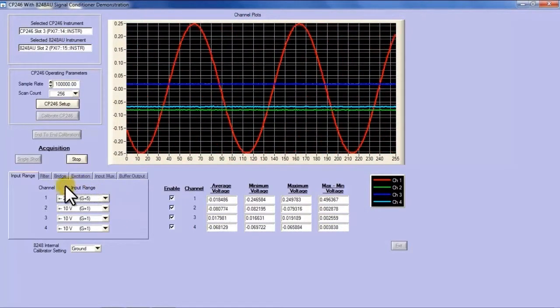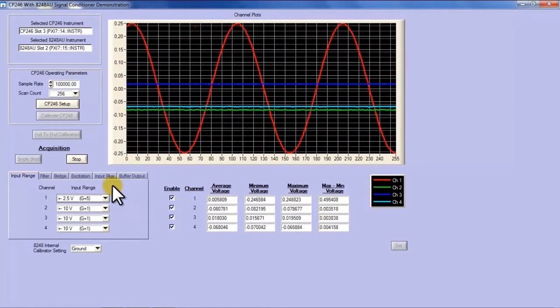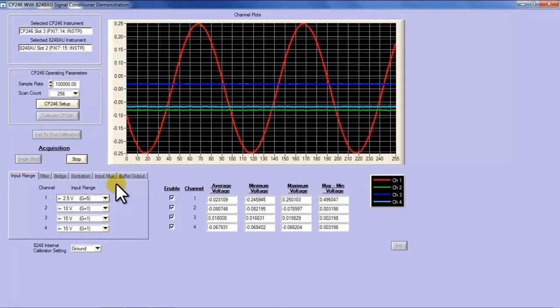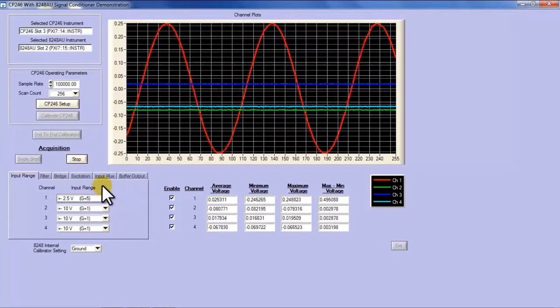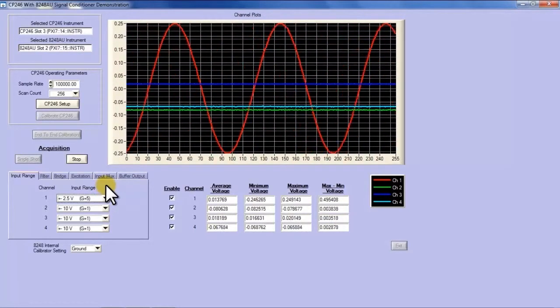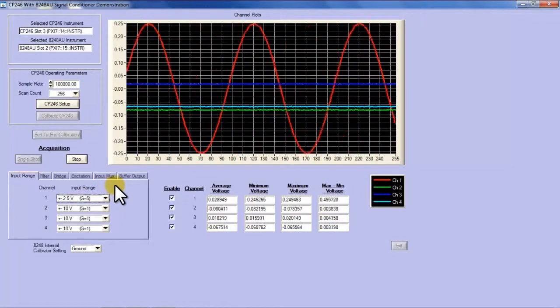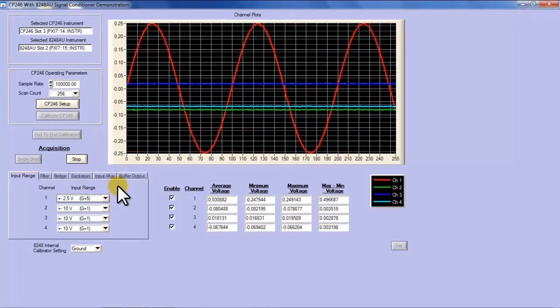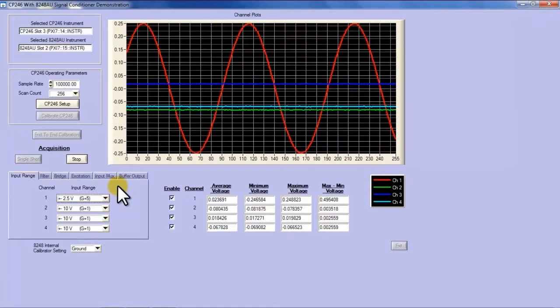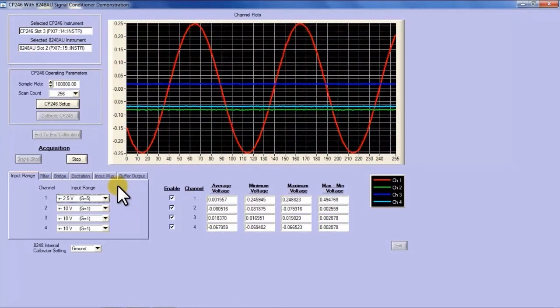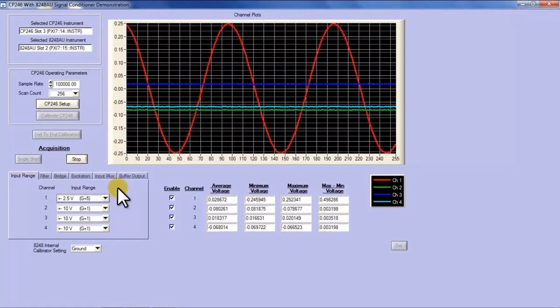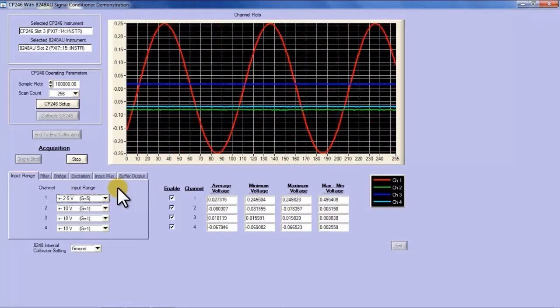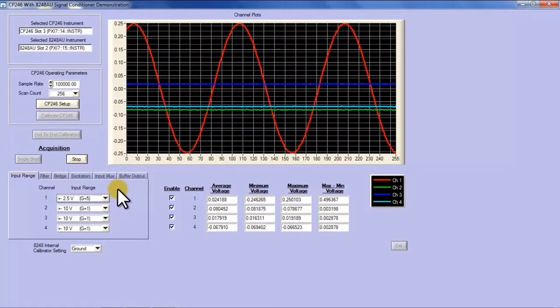This is great in the effect that it is doing the amplification but the problem that we're having with this is that I'm not getting a referred to input signal measurement. I'm getting a referred to output measurement because I'm taking an input signal and doing an amplification of it. In order to get the real true value of the input I really need to do an end-to-end calibration.